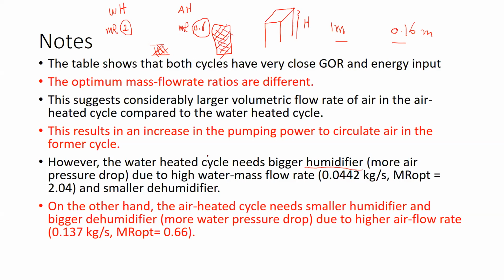More water also creates a higher pressure drop of the air, which is fine, we're not looking at pressure drop at the moment, but we're looking at a flow rate ratio of about 2, so the flow rate of water is twice the flow rate of air. With more water, you need to provide more opportunity for the evaporation transfer to occur. The packing material provides a surface area for the water to stay on, so you need a larger surface area because of the higher water flow rate, creating a film of water on these surfaces that transfers heat and mass to the air.